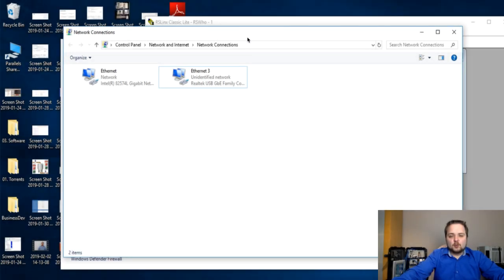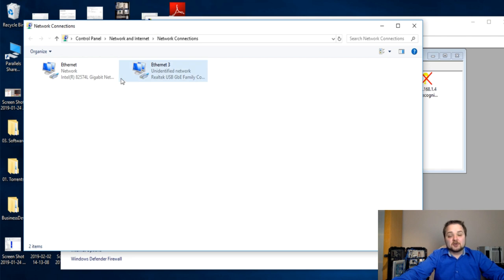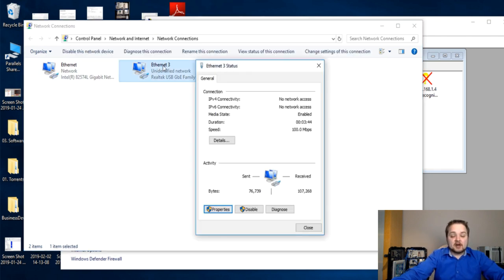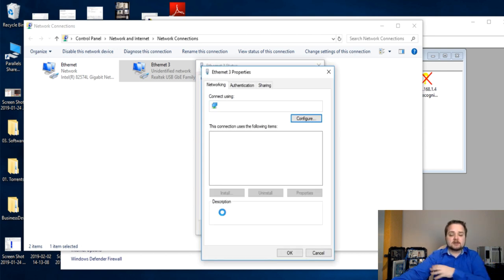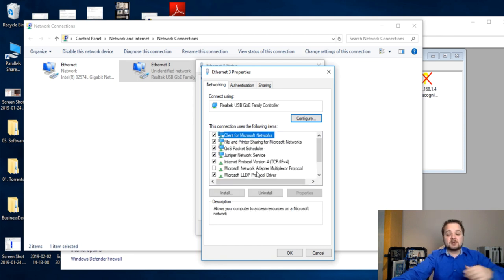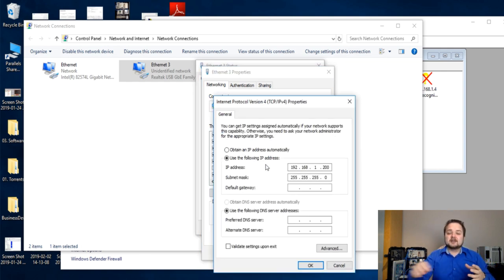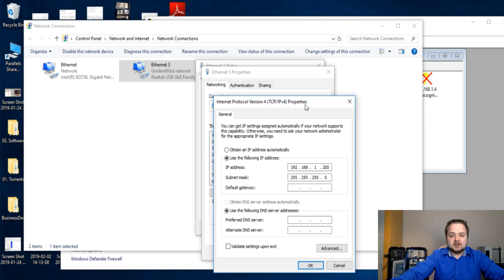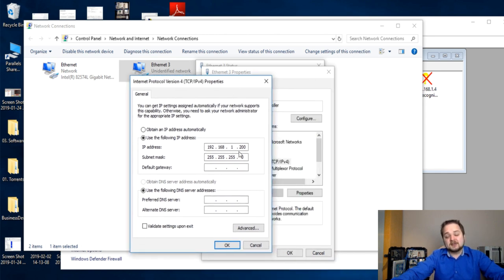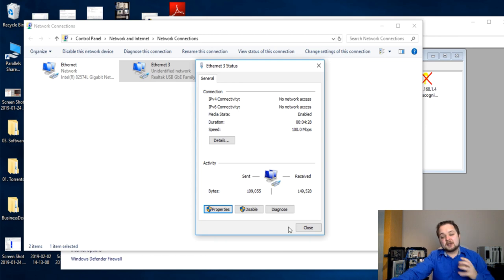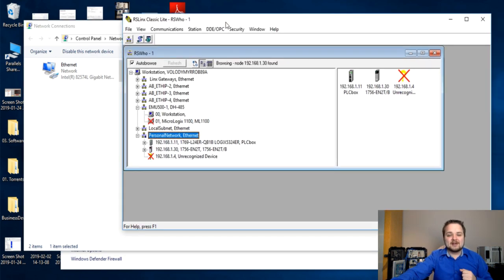Here on the Windows desktop I have two different ethernet drivers because I'm running a virtual machine. We need to set up the right IP addresses based on the PLCs, and we need to be on the same subnet as the PLCs to communicate. The IP address I'm using on my computer is 192.168.1.200, on a private subnet with a mask of 255.255.255.0. We'll hit OK, then check communications to the PLCs from our laptop using RSLinx Classic.